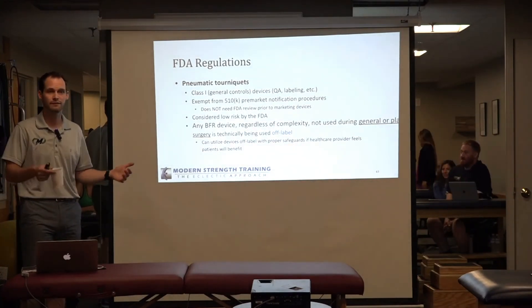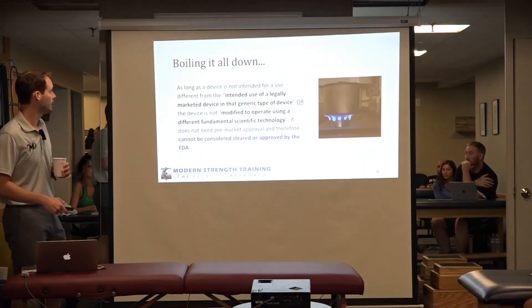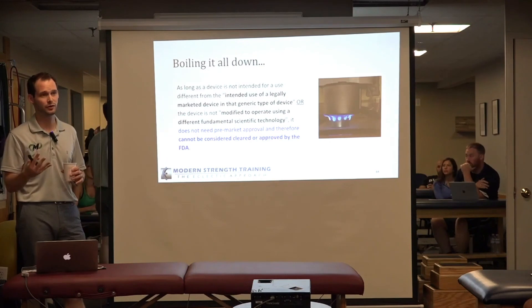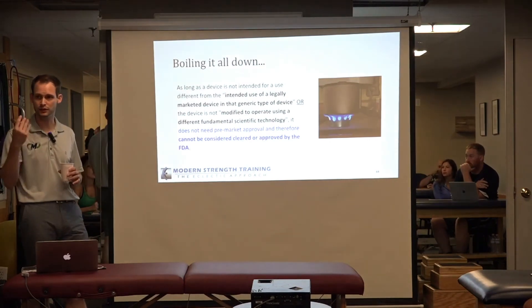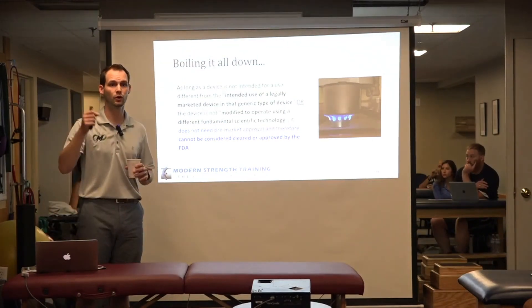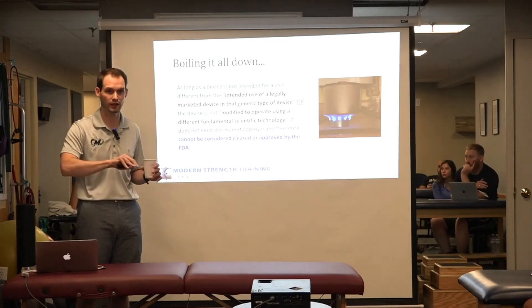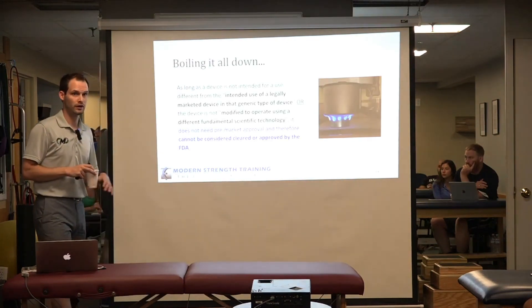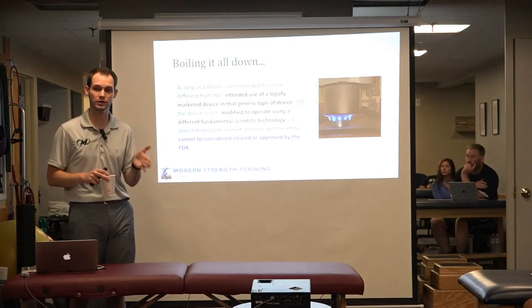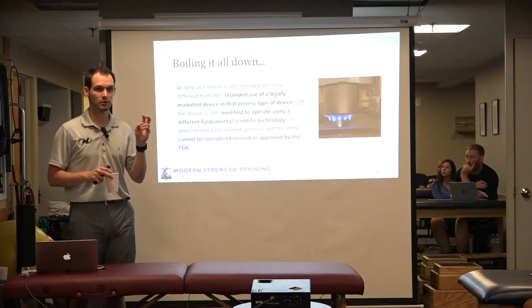The ones that we use have very good control systems and everything going for them. But to my knowledge — and I've spent countless hours on the phone with the FDA trying to get answers — there is no BFR device that is approved or cleared by the FDA, only listed, which is the lowest stringency level. Furthermore, anything under the pneumatic tourniquet category is considered a therapeutic device, and there is no device specifically cleared or approved for clinical rehab populations.